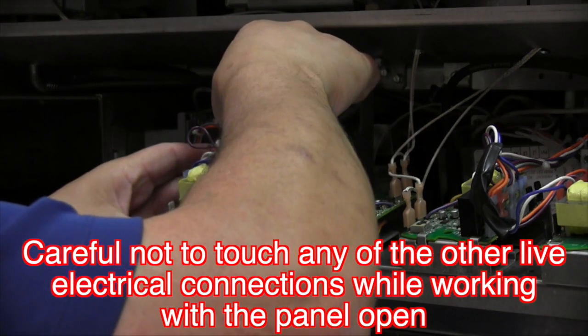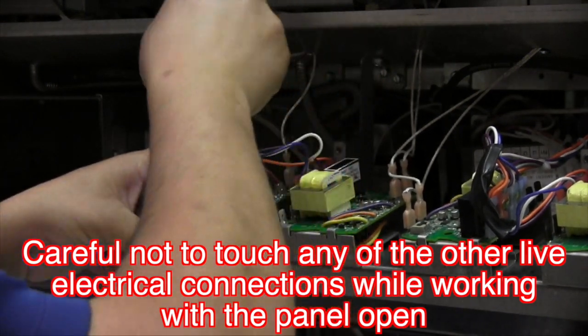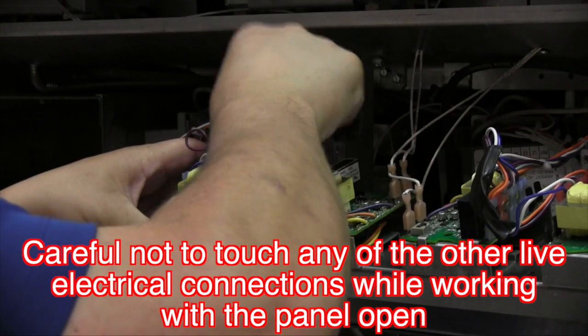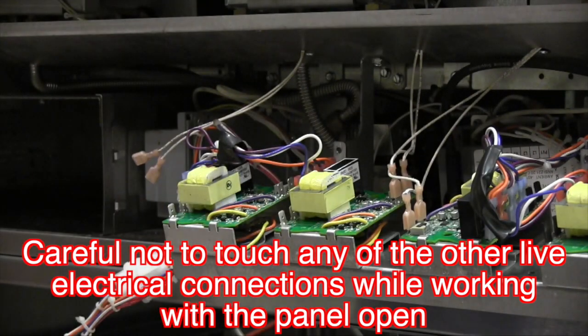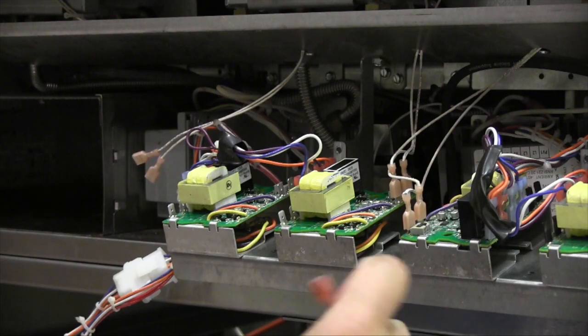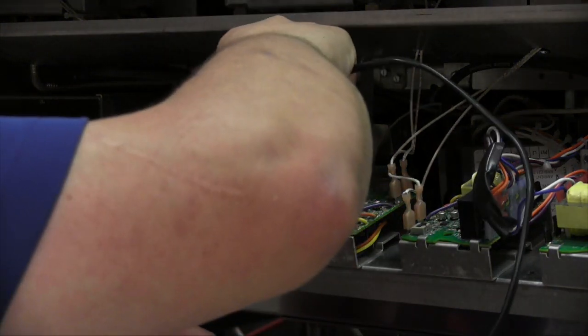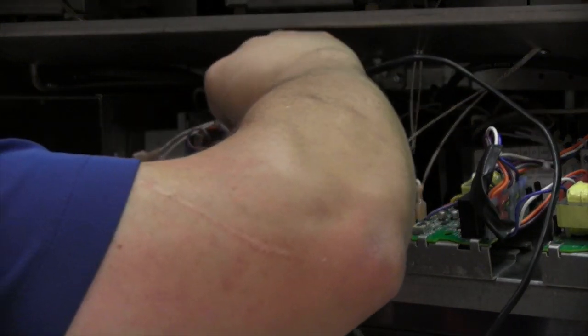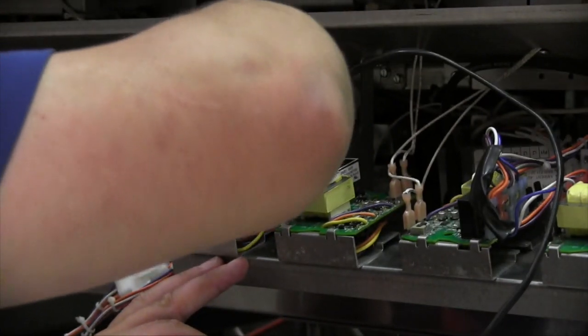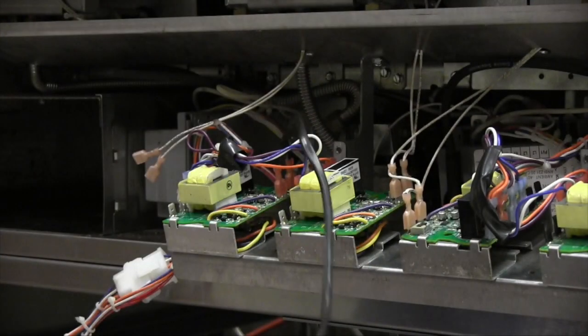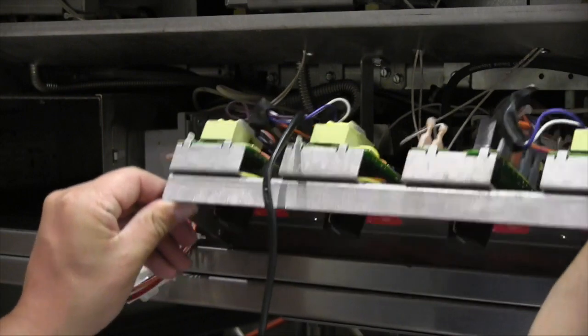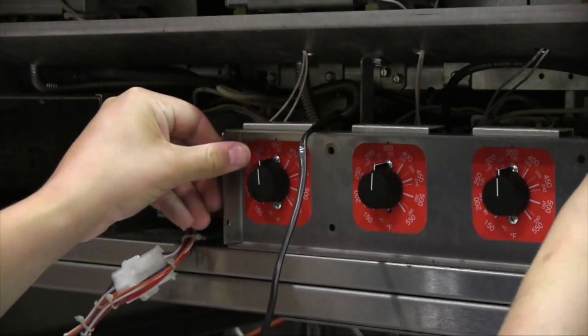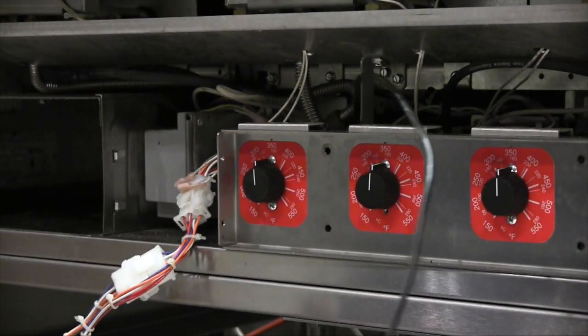Start left to right or right to left, and only unplug wires to one controller at a time so that you do not mix up the temp probe wires with the wrong controllers. Remove the temp probe wires from one of the controls and attach your calibration tool wires to the same terminals you removed the temp probe wires from. It does not matter what wires go to what terminal. Flip the control panel back into the upright position.